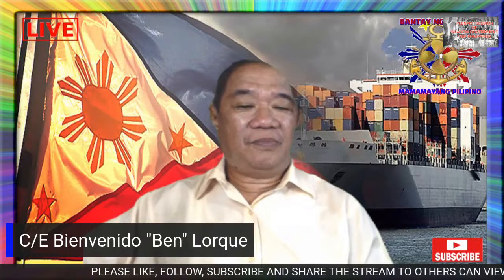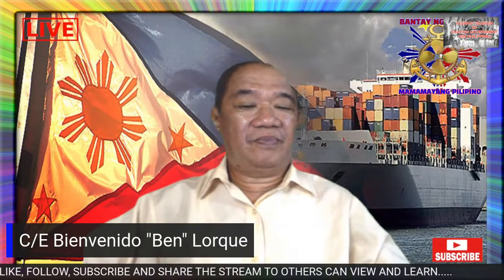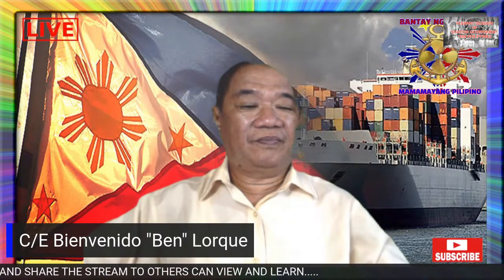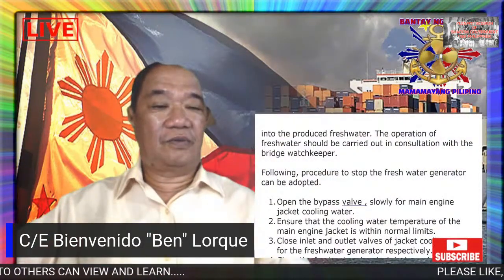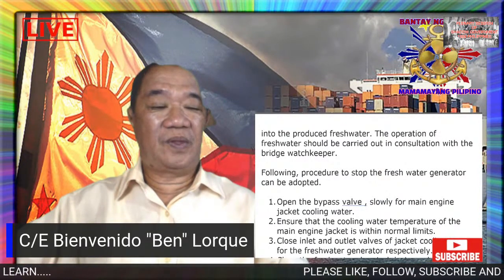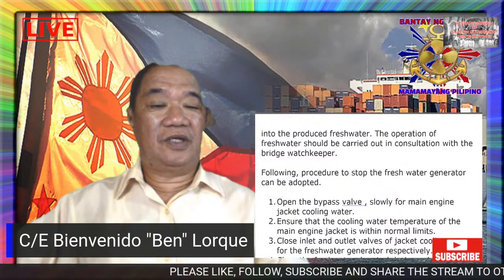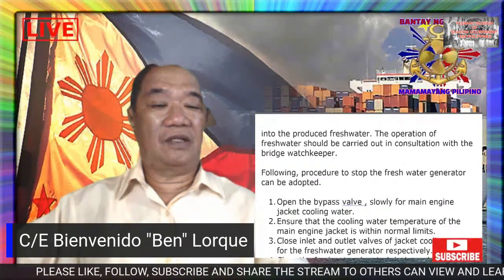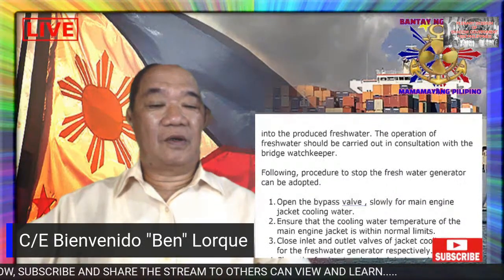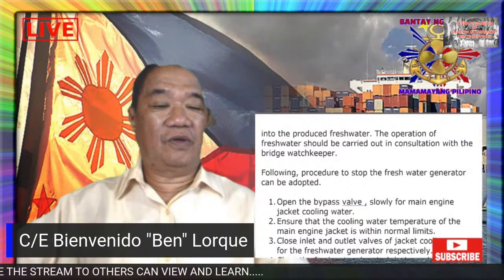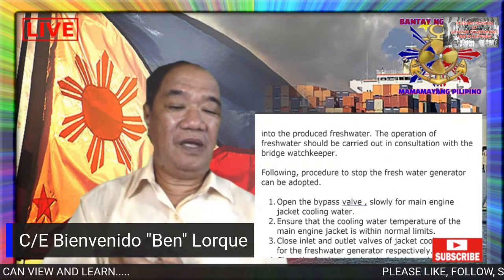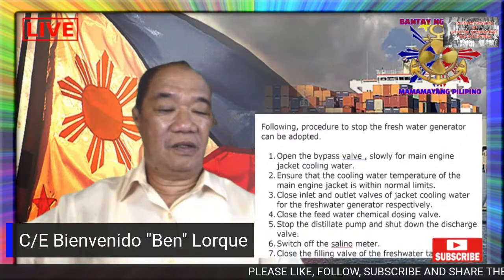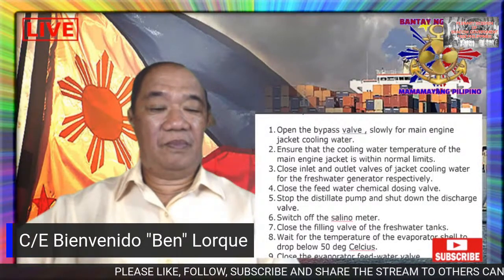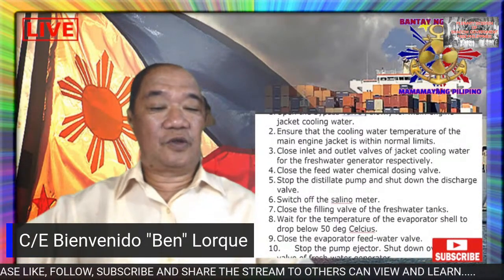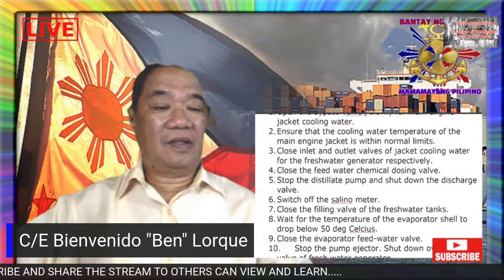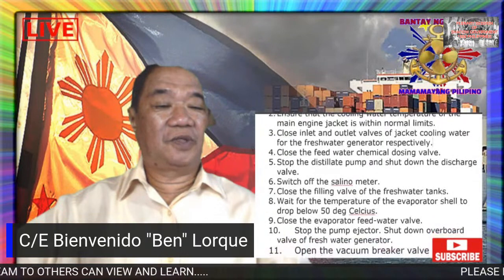So to stop the freshwater generator, you have to open the bypass valve slowly for the main engine jacket cooling water. So sa bypass valve na yan, balik-balik na lang tubig doon, hindi na papasok doon sa freshwater generator seal. Ensure that the cooling water temperature of the main engine jacket is within the normal limit. Close the inlet and outlet valves of the jacket cooling water for the freshwater generator respectively. Then close the feed water chemical dosing valve. Stop the distillate pump. Shut down the discharge valve. Switch off the salinometer. Then close the filling valve of the freshwater tank.